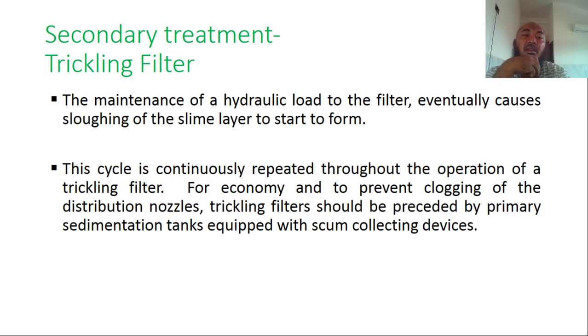The maintaining of hydraulic load to the filter eventually causes sloughing of the slime layer, and a new one starts to form. This cycle is continuously repeated throughout the operation of the trickling filter. For economy and to prevent clogging of the distribution nozzles, trickling filters should be preceded by primary sedimentation tanks equipped with scum collecting devices.